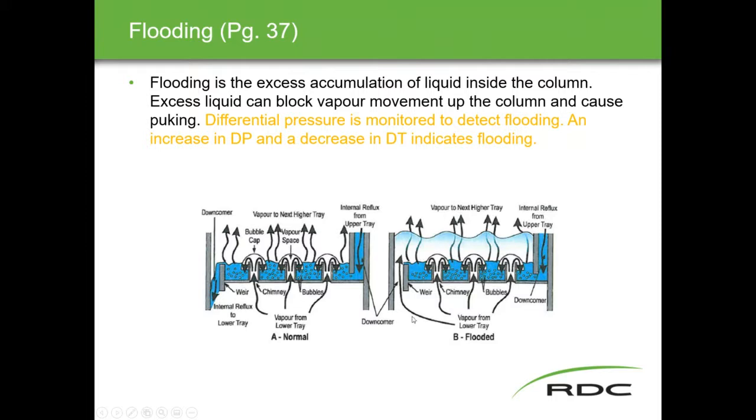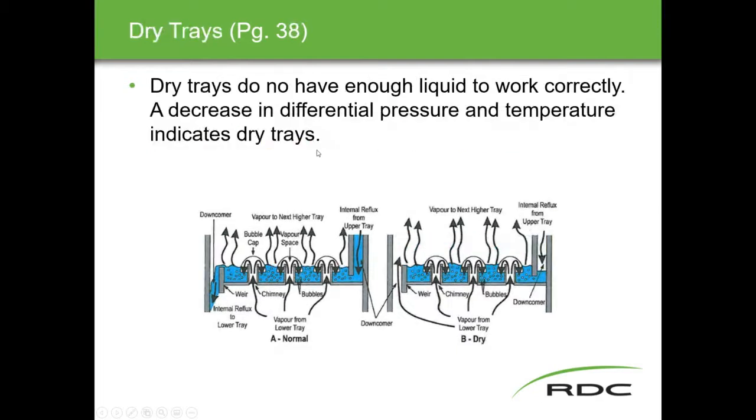We'll also have a small difference in temperature, because the vapor again is not going up there to do any heating. So it's going to create a decrease in the differential temperature. The temperatures are going to be closer together. So flooding is indicated by an increase in differential pressure and a decrease in differential temperature. Long story short, that was a little bit painful.